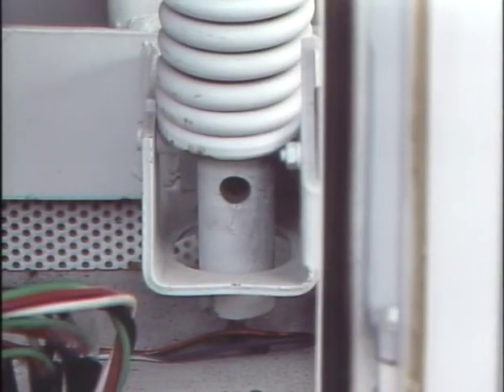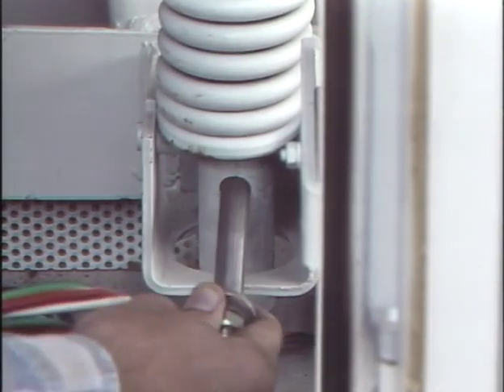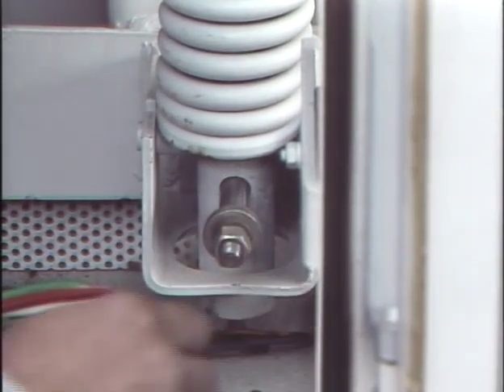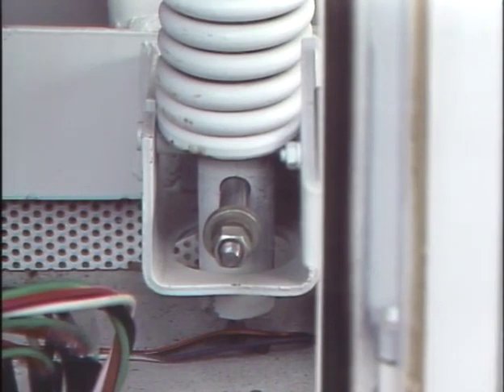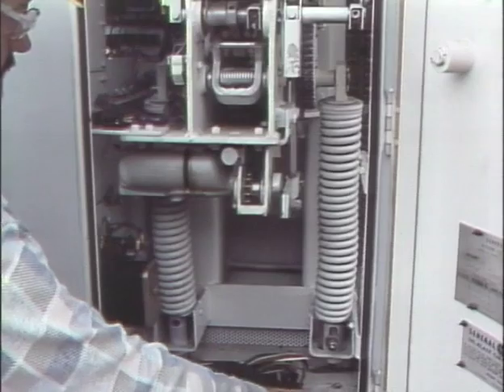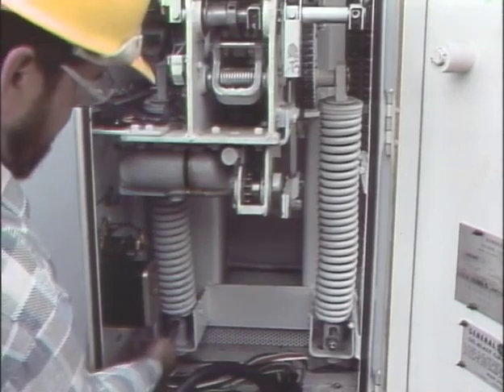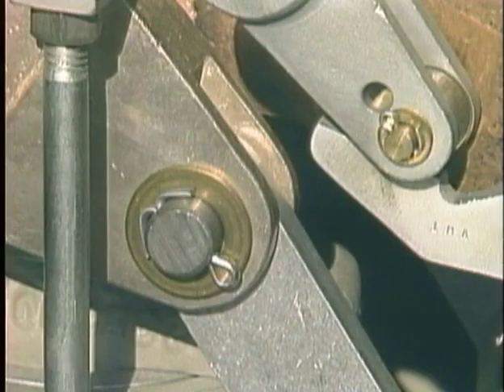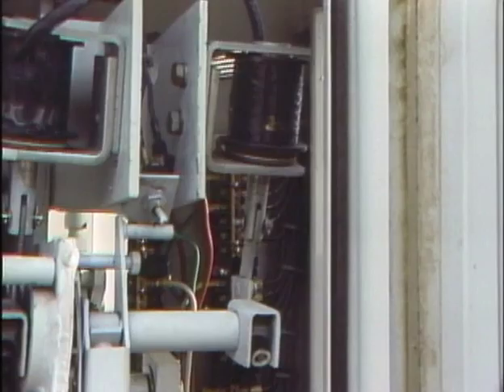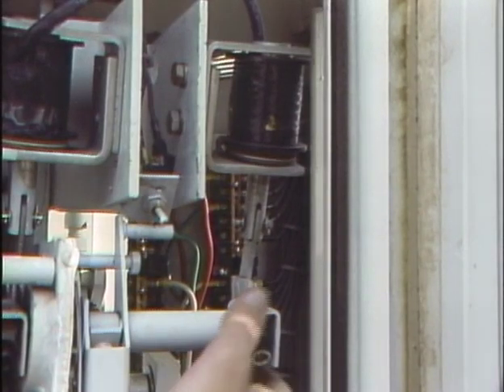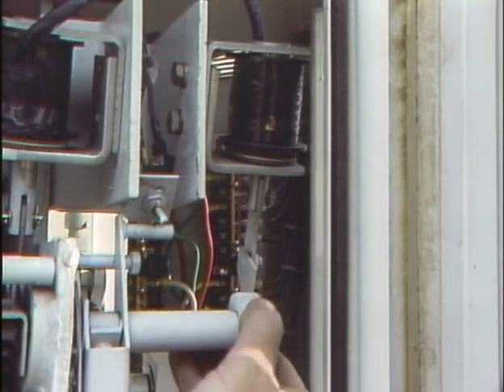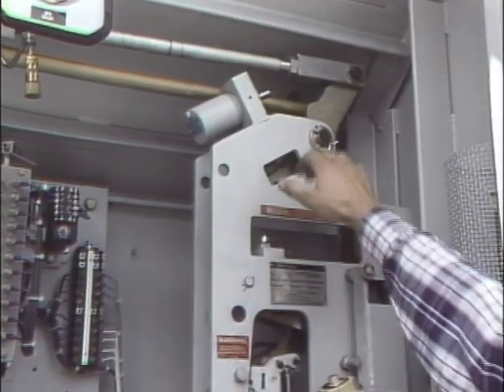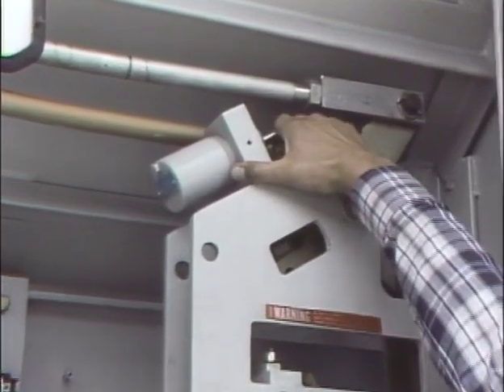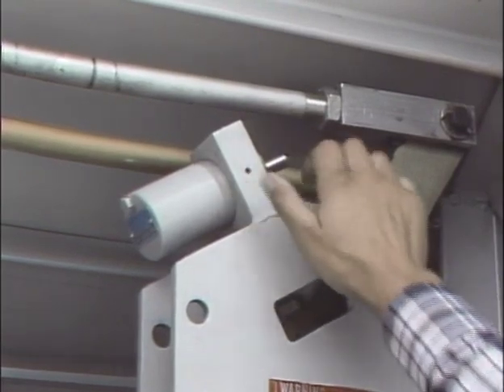In addition to mechanical checks of the breaker, a number of mechanical checks are made of the breaker's operating mechanism. For your safety, the operating mechanism must be disabled or blocked so that it cannot operate while you're checking it. All hardware, such as nuts, bolts, washers, cotter pins, and snap rings, is checked to make sure it's secure. The plungers on all control coils are checked by hand to make sure that they move freely. The dashpot rod on each dashpot is moved by hand to make sure that it too moves freely.